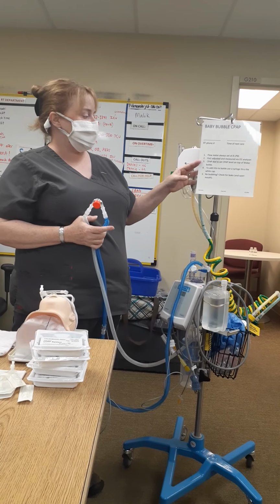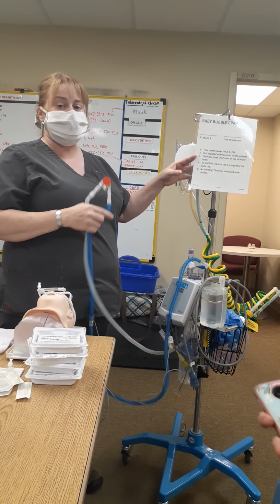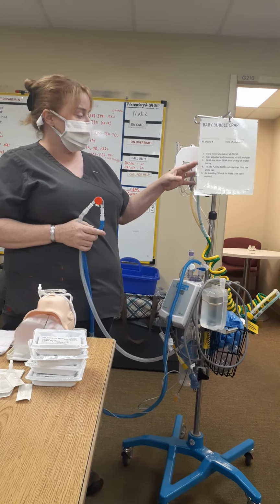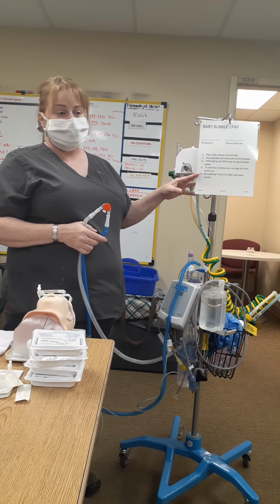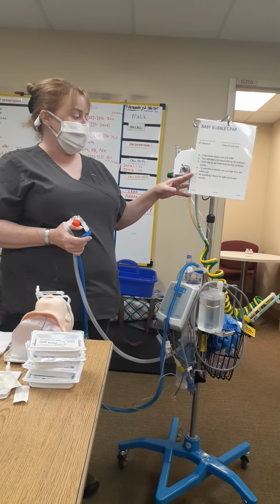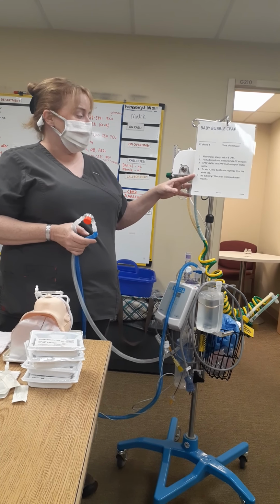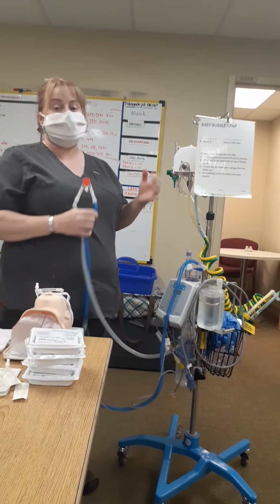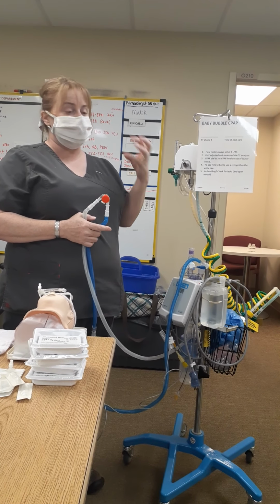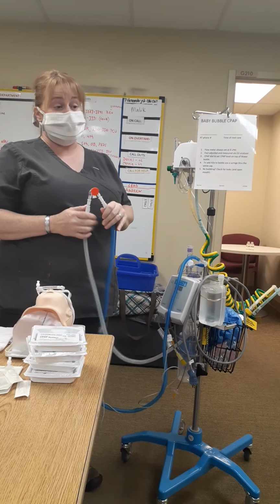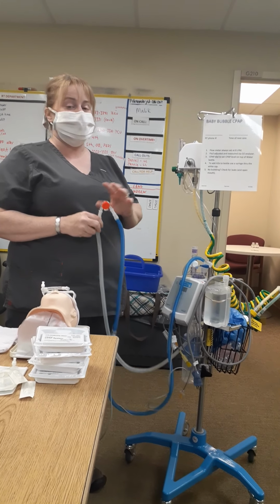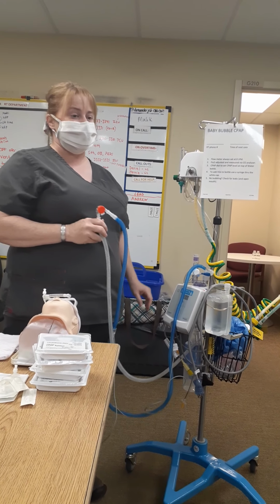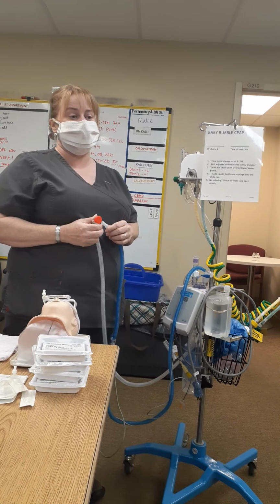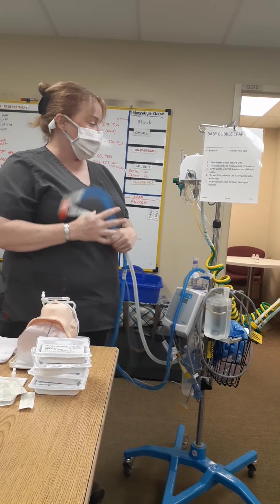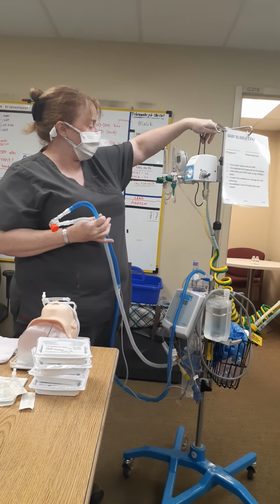The CPAP dial is set to the CPAP level on the top of the bottle, which I will show you in just a minute. To add water to the bottle, use a syringe through the white cap, which I'll show you in a minute. If there's no bubbling, which is going to be the most common thing that's going to happen, baby's going to desat and there's going to be no bubbling. Check for leaks. That's the first thing. Does the baby have an open mouth? Do you have a poor seal around your mask or your prongs? And then if that's not the problem, then work your way back from the baby all the way back to the machine, looking for anything to be unplugged or a cap that's missing or something like that. So there's our little sheet.